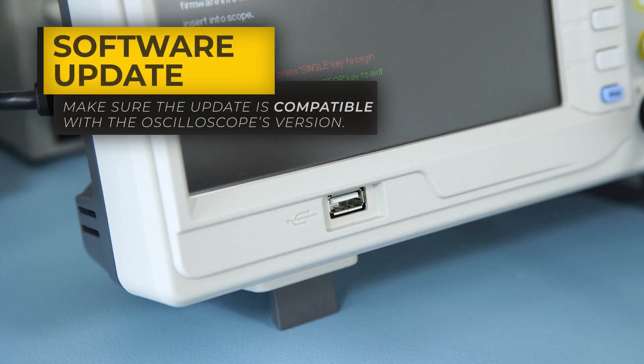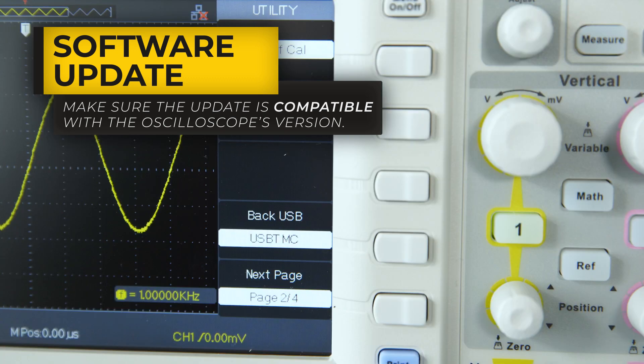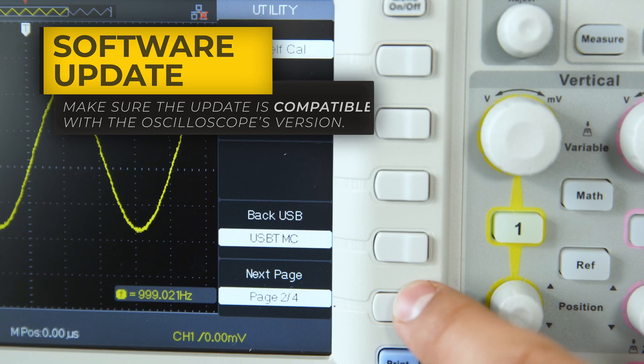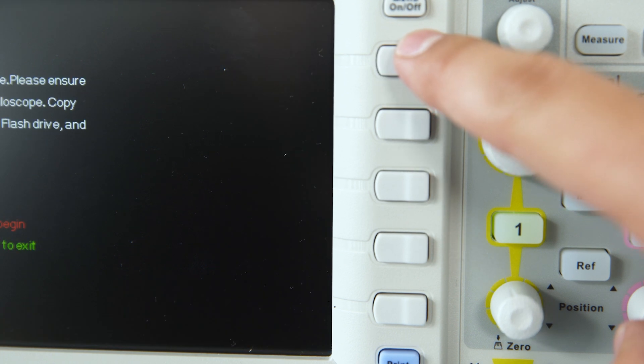If there is new software available, the user can update the Oscilloscope by inserting a USB flash drive into the front USB port and running the update by pressing the single key.